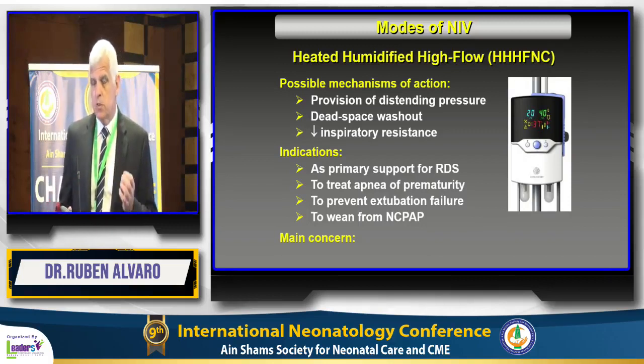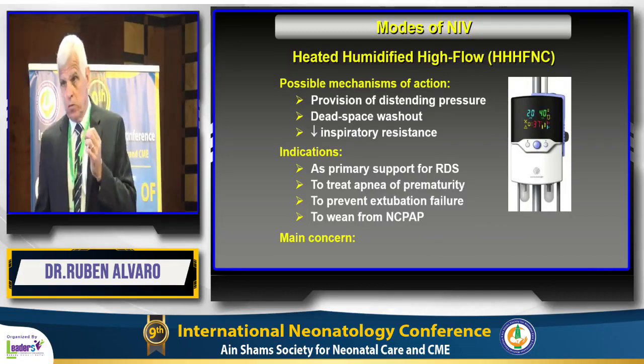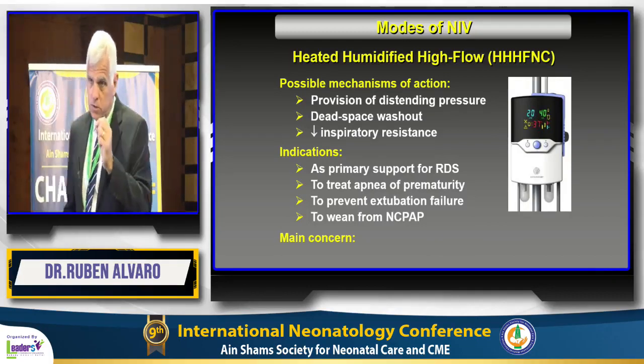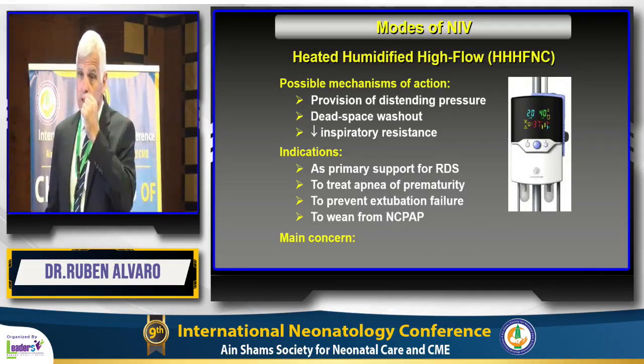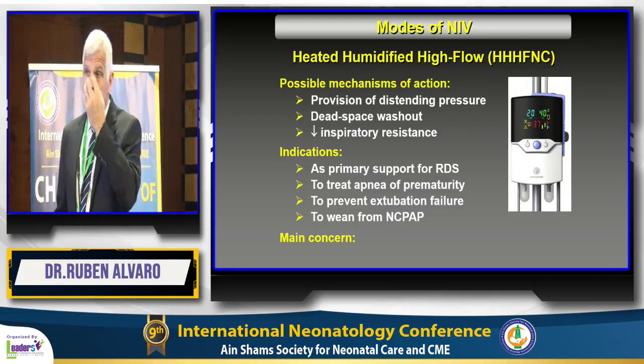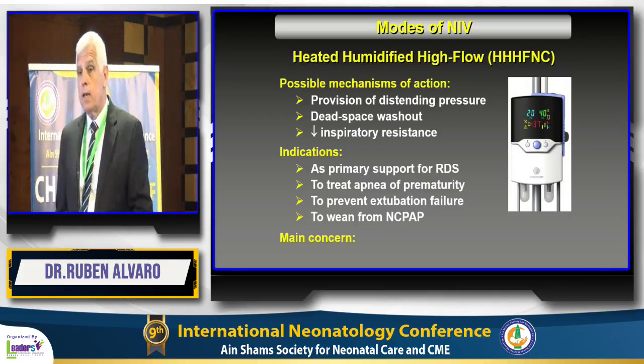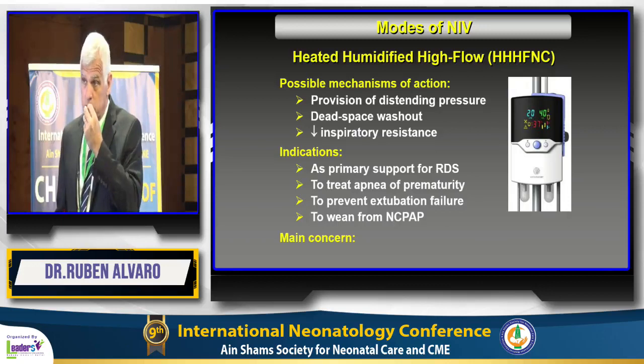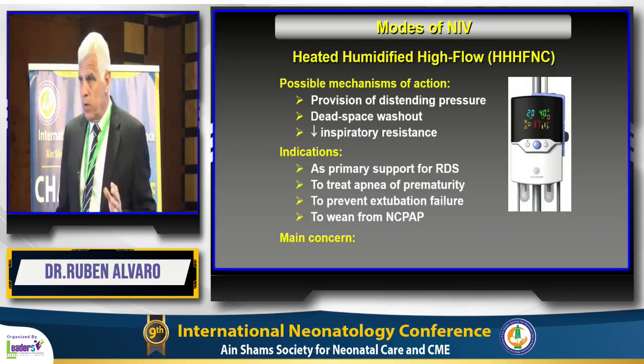What's the main problem with high-flow nasal cannula is you have no idea how much pressure you're using. Because the pressure does not only depend on the flow you're using, it also depends on the amount of leak you have between the prongs and the nose, so that depends on the size of the nose, and also on the size of the prongs they're using. So you have no idea how much pressure you're using.